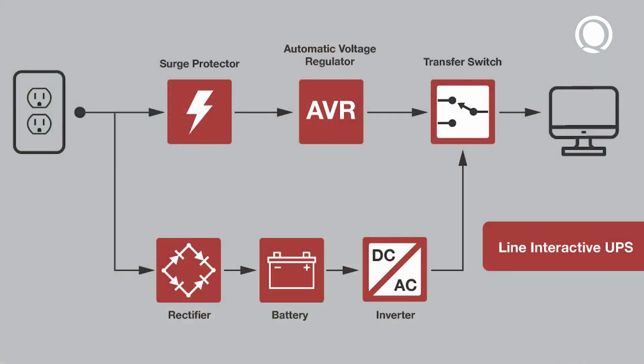The next level of UPS is similar, and it's called a line-interactive. We still have the power conditioning. Power comes in, goes through a surge type protector, cleans up the power. From there, it goes into an auto transformer. There's multiple names for these. Sometimes it's called an AVS, automatic voltage regulator, or automatic voltage source, or an AVR. And out of that AVR into the transfer switch, and then to the computer.